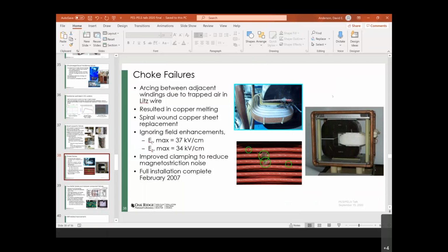The problem with the Litz wire is that when we submerge it under the oil, we don't put a vacuum on the tank at all, so whatever air is trapped between the different Litz conductor elements has to work its way out just by diffusion. That really isn't feasible because the spaces are quite small, and eventually corona ensues in those locations, causing the insulation systems to fail. So going with this flat wound conductor spiral configuration on the right really solved all those problems, and it's been quite reliable.